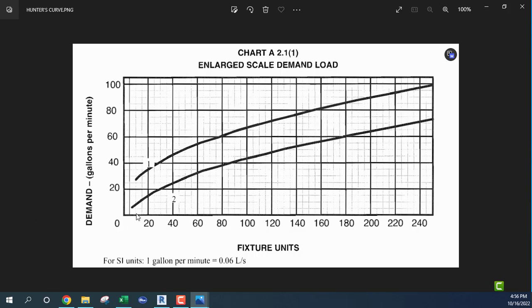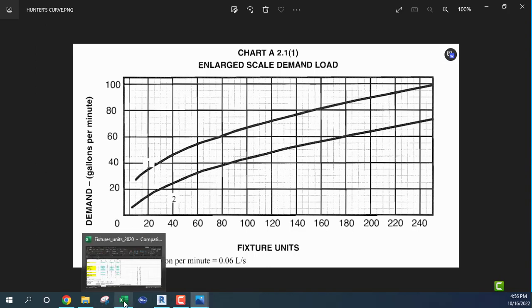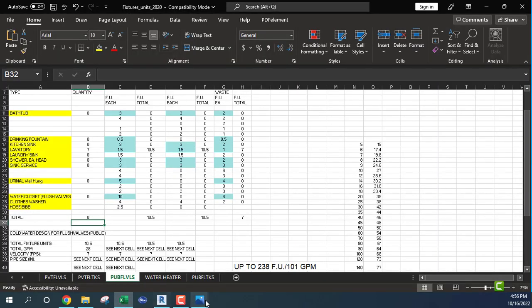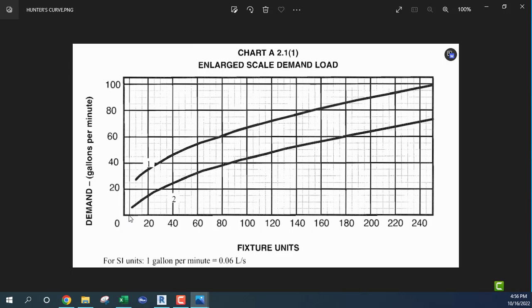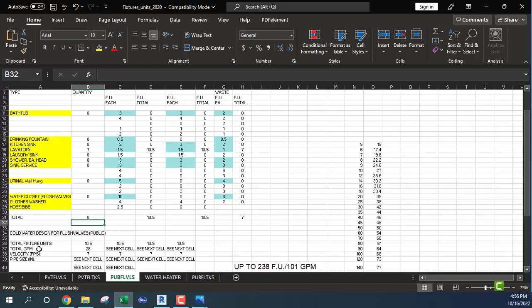So 10.5 fixture units is 28 GPM. Let's check that: 5, 10, 15, 20 — five fixture units, ten fixture units. We go up on the Hunter curves — this is for flush valves, this is flush tanks — Hunter curves with an S. I have 10.5 fixture units; at 10, 20, 25 — yeah that's about right. So 28 GPM, that's correct looking at the calculations.